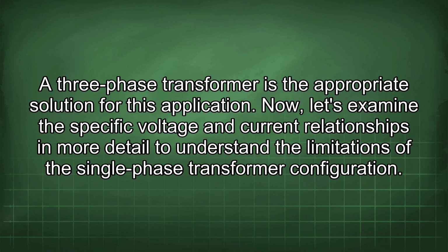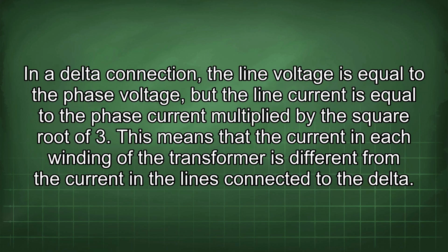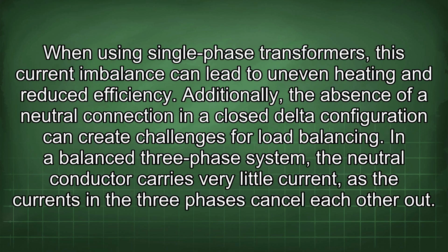Now, let's examine the specific voltage and current relationships in more detail to understand the limitations of the single-phase transformer configuration. In a delta connection, the line voltage is equal to the phase voltage, but the line current is equal to the phase current multiplied by the square root of 3. This means that the current in each winding of the transformer is different from the current in the lines connected to the delta. When using single-phase transformers, this current imbalance can lead to uneven heating and reduced efficiency.